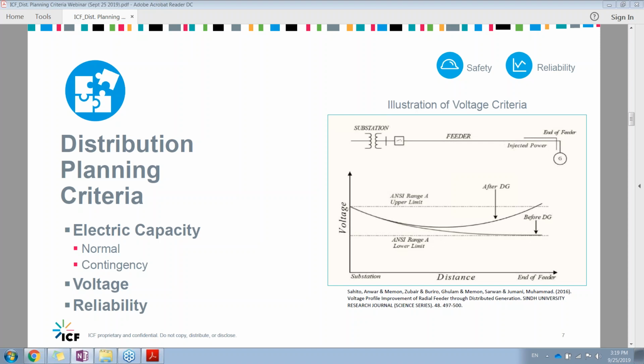In terms of voltage criteria, the second bullet point on the list here, customer equipment is designed to operate within a range of voltages that correspond with utility planning criteria. And these are based on industry standards. Over on the right-hand side of the screen is an image that shows a source of electric power, the substation on the left, and then just a conceptual feeder where there would be customers distributed along the line potentially. And then at the very end is a distributed generation unit or DER. We could assume that this is a solar device.